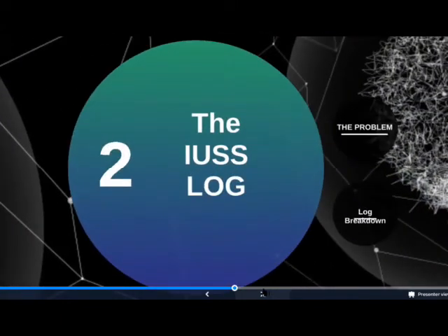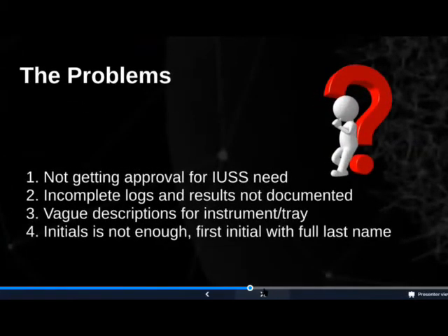So the IUSS log, let's start with some of the frequent problems we've seen over time. Not getting approval for the IUSS need. Remember, this is the first step. Can we do this? Once you get this answer, you actually want to make sure you document that name on the IUSS log. Incomplete logs and results not being documented. A lot of people may have actually checked the results and know, indeed, yes, I can use this. It said it was negative, I'm straight. But they'll forget to actually put it in the documentation. Remember, that protects us. So we need to make sure that we go back in there and document it. And also, your approver is going to take some time to go back and do the same thing.